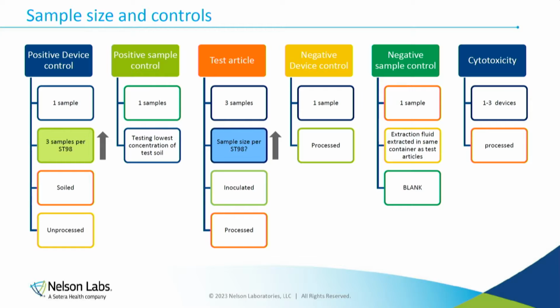Sample size. Sample size has increased, right? There was only 3 required. Now that's taken out. Now it's the manufacturer's responsibility to determine what sample size you're going to use, and that depends on the criticality of your product and the complexity of your product. So how complex is your product and how critical is your product? Let me give you an example. Flexible endoscopes are critical and complex, so there will be 9. All surgical devices will be 6. Non-critical devices where there's no risk will be 3, right? So that is how you would figure out your sample size.